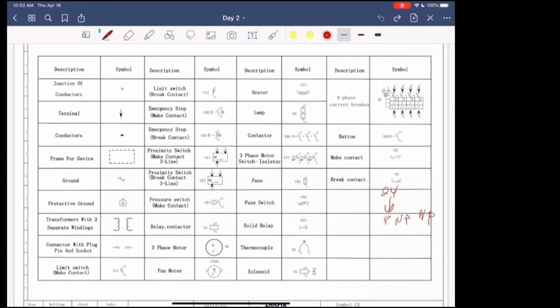The other thing that you have to remember that a lot of people don't really keep in mind when they're reading blueprints is the limit switches. So a normally open or a normally closed limit switch is the status of the limit switch when it's not being activated. For example, if you close a door and the limit switches are activated, then the conditions change. They'll go from an open to a closed position or a closed to an open position.